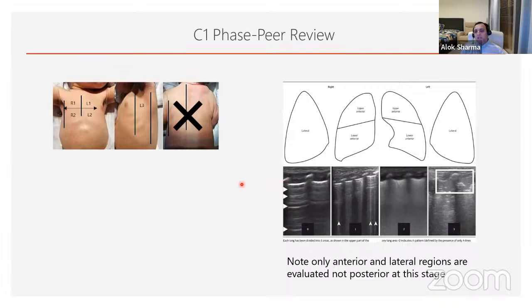There are machines which have auto gain settings. Auto gain basically adjusts the background gain. Now, there is spatial gain and there is transverse gain. Each machine is different. In our machine, the GE, we use transverse gain. You can use auto gain functions, but sometimes the auto gain function, if your probe is not in good contact, defaults to settings which might not be optimum. So don't hesitate to play with the gain.